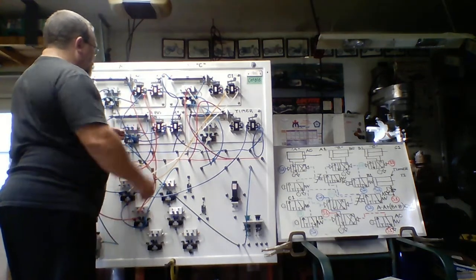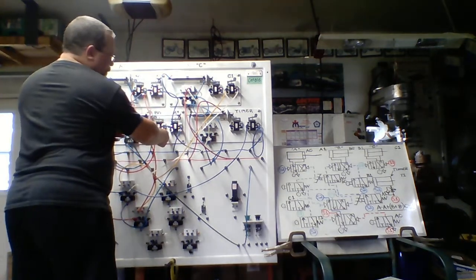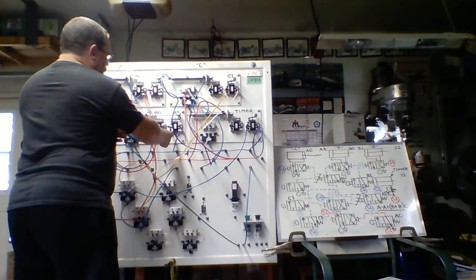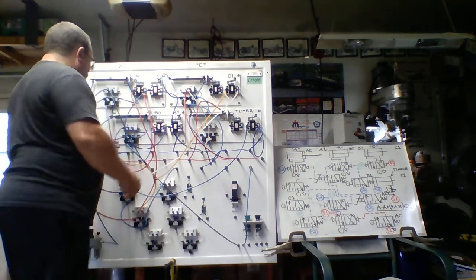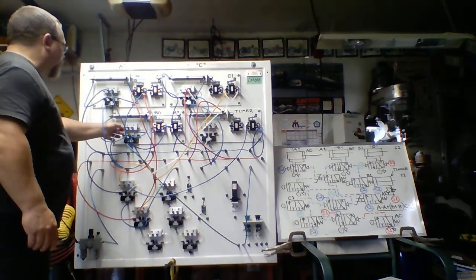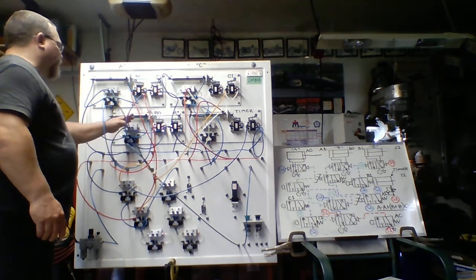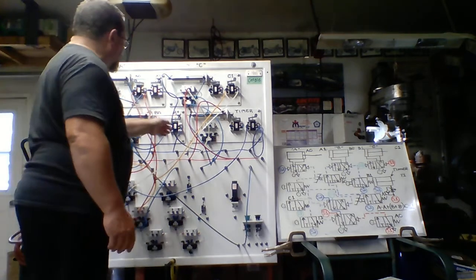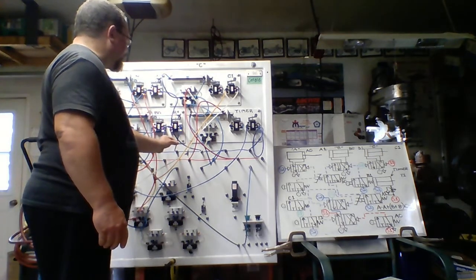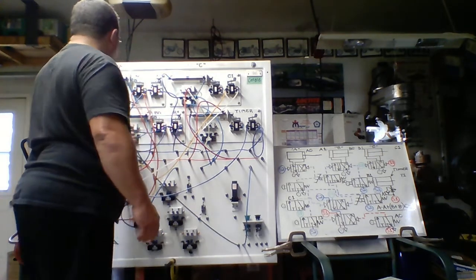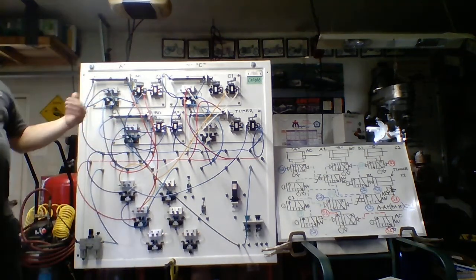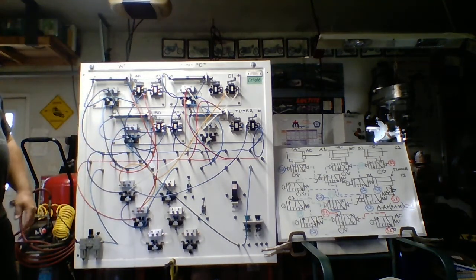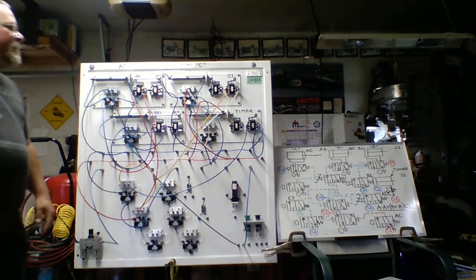We come out of A1, and we're supplying, as I mentioned prior, in series to B0. Supplying B0, and this will come out and pilot the valve which is going to control B extension or retraction. And of course, when it extends, it gets on B1. Again, it's tied directly into the manifold. It also comes over in the pilot. So at this point in time, B will reciprocate, and it'll continue to reciprocate.